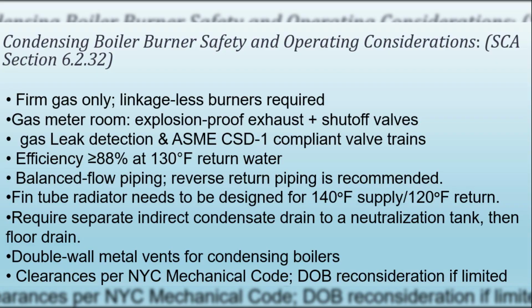This section applies when condensing boilers are retrofitted or replaced in existing heating systems. The standard heating approach for new schools is heat pumps, so condensing boilers require special approval. When allowed, boilers must run on firm gas only and use linkage-less burners for safety and precision. The gas meter room must be equipped with explosion-proof fans, lighting, and switches. Gas shutoff valves must be provided both at the firm gas main and inside the gas meter room. Each boiler must have a gas leak detection system, and all valve trains must comply with ASME CSD1.